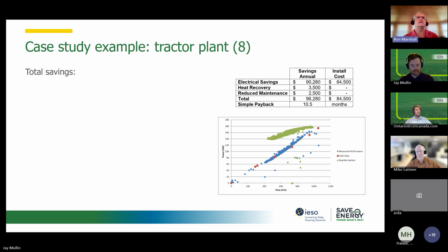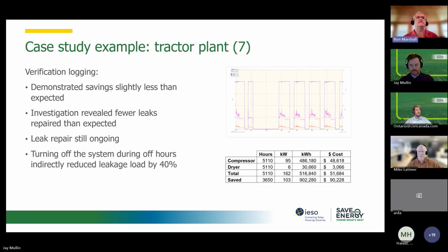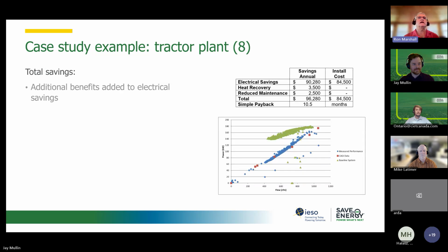So as I mentioned, slightly less than expected savings were gained. We can see the time, weekends and nighttime activity on that chart to the right, where they shut off the compressed air system. So there's really no operating costs there other than that small compressor, right? So there's still ongoing leaks in that. So as I said, turning off the system reduced the leakage load by 40%. So pretty significant savings. Next slide.